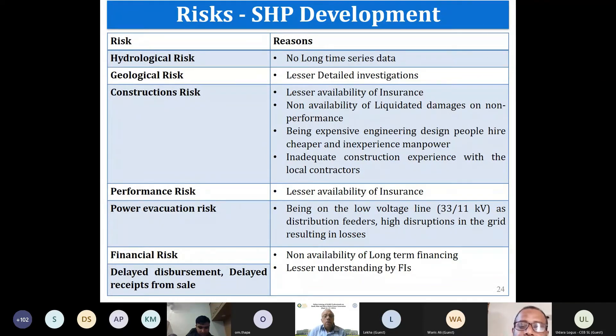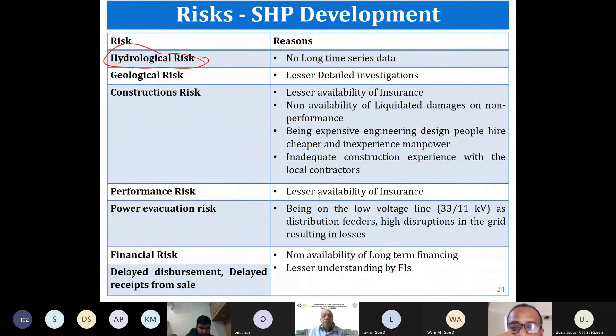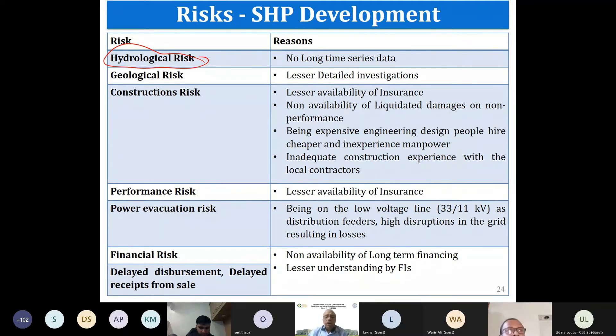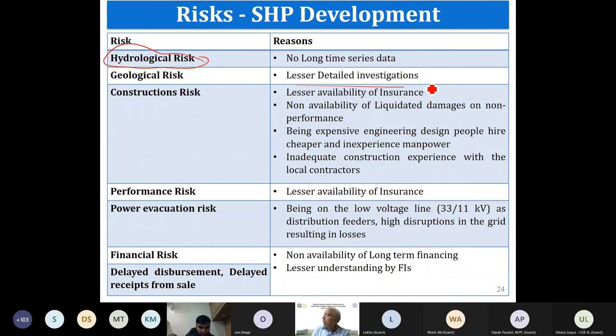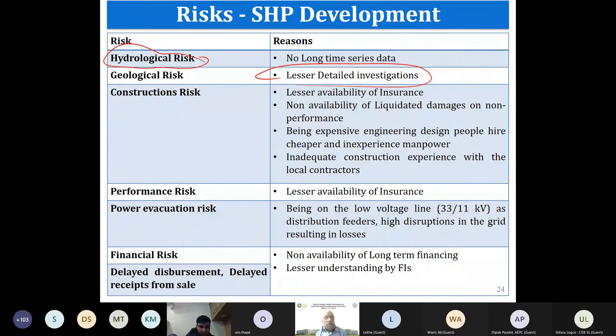Key risks include: hydrological risk — small hydro is on small streams where nobody measures discharge data, so long time-series data is unavailable; geological risk — Himalayan countries have young geology with significantly higher risks compared to mature geology like Sri Lanka or southern India, where geological risks are very low.